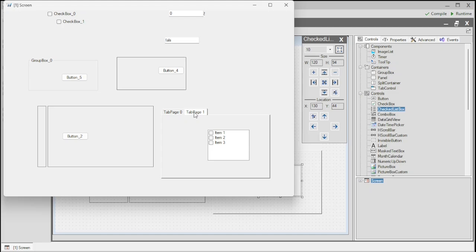However, there is an incorrect usage here. In SCADA projects, instead of creating separate screens, developers sometimes use full-screen tab pages. Each tab page actually represents a full screen. For example, if we assume there are 10 pages, this means 10 screens are open at the same time. From a performance perspective, especially on low-performance systems, we do not recommend using full-screen tab pages in this way.